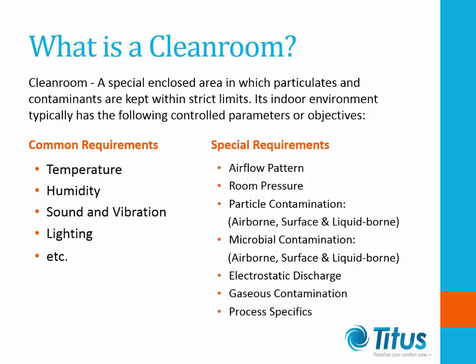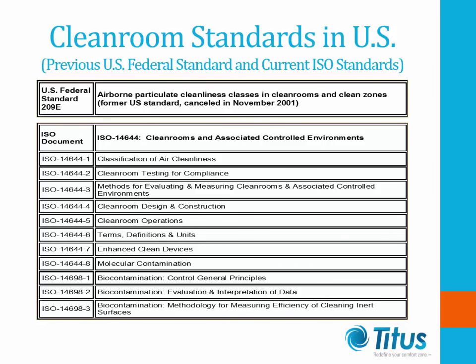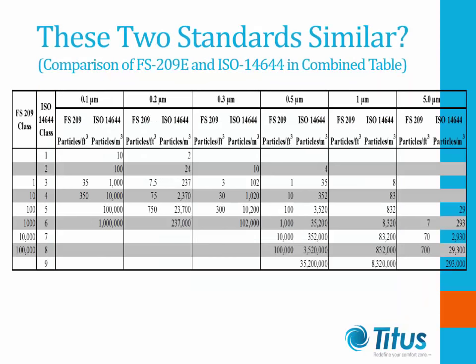Before 2001, the US utilized Federal Standard 209E, which was the latest version before ISO standards were introduced. After 2001, the US and many other countries adopted ISO 14644 series. Parts 1 through Part 8 are basically for particles and molecular contamination. Another ISO series, 14698, including Parts 1, 2, and 3, covers biocontamination.